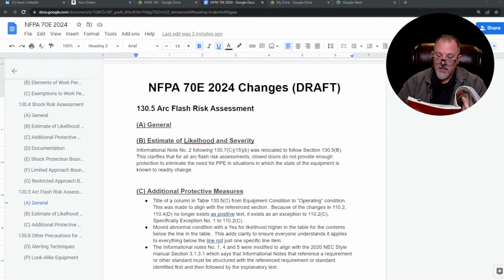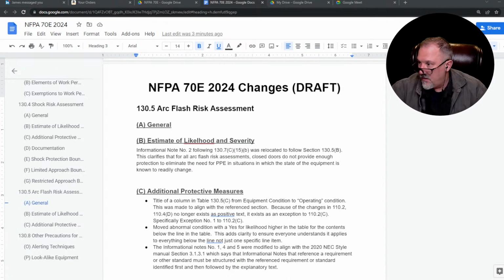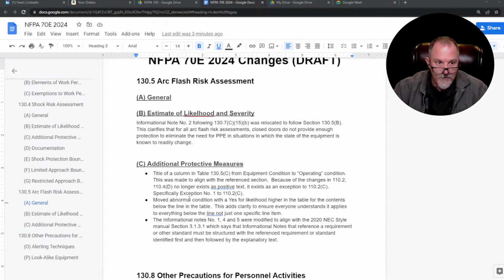It talks about the arc flash risk assessment performed in accordance with 130.5(G) indicating that arc flash PPE is required, and the arc flash PPE category method is used for the selection of PPE, and incident energy analysis shall be required. And the informational note says, in most cases, closed doors do not provide enough protection to eliminate the need for PPE in situations in which the state of the equipment is known to readily change. I remember we talked about this already. People argue that with me all the time, and I just go to that informational note.